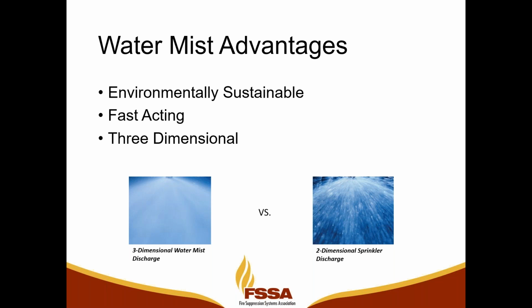Water mist is fast acting. So when we're talking about a machinery space or a turbine enclosure, we are using our water mist system in conjunction with the same kind of detection and control systems that we use on gaseous agent systems. So we're potentially detecting the very first molecules of combustion and discharging our system. So the system's going to go off hopefully before the fire can do any significant damage. And that's in contrast to a sprinkler system in a light hazard application where we might be waiting for a bulb to break and a nozzle to open that way.